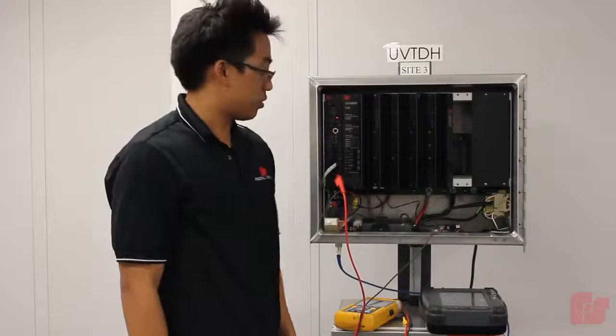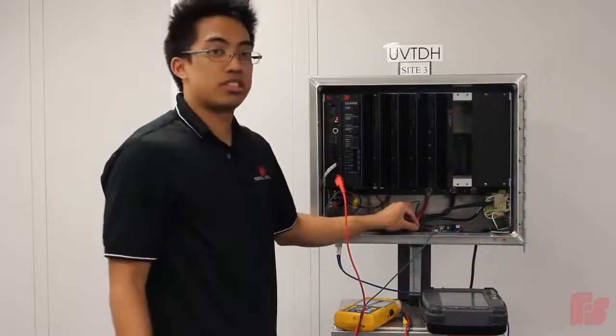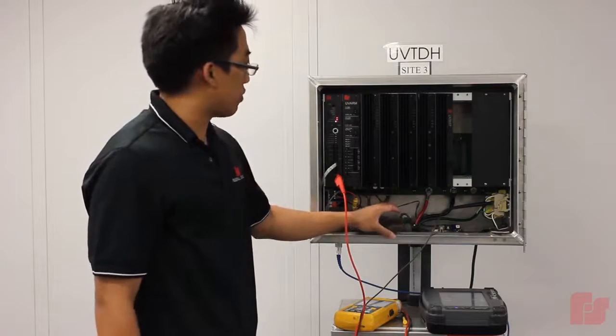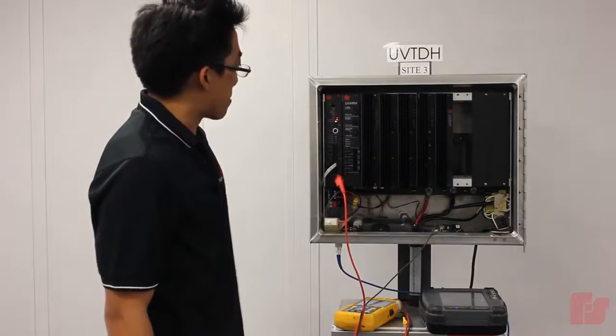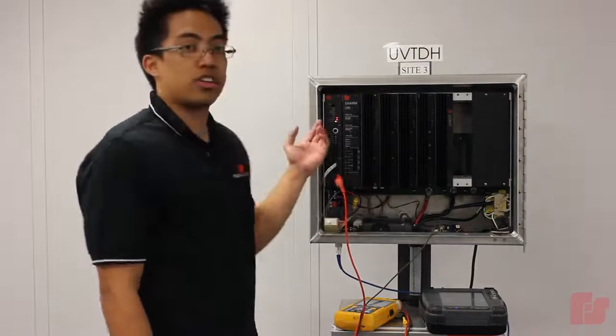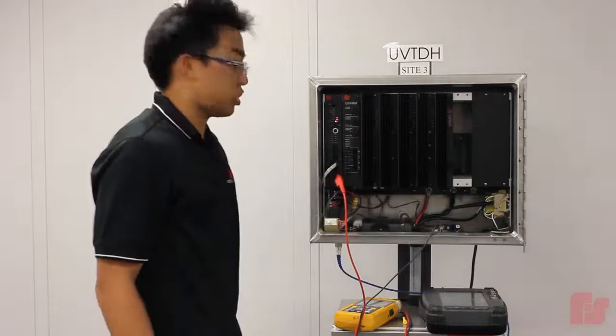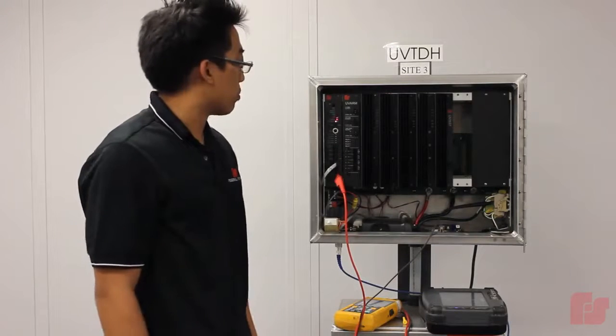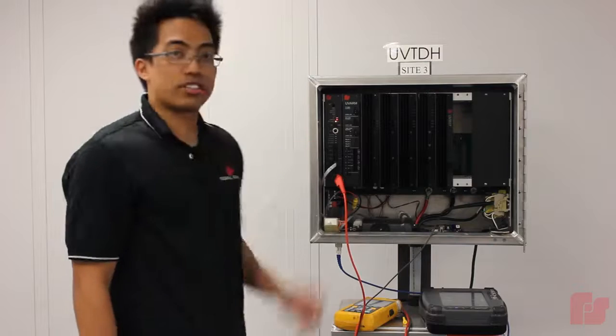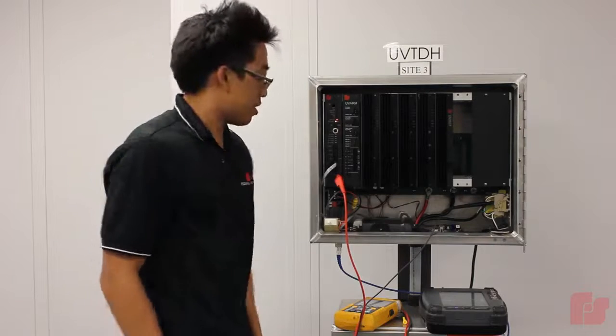So now we're going to go ahead and turn on the calibration tone. And as you can see here, the radio is receiving it and so is the controller board. So the RX level is kind of low and to adjust it to the proper level, we're going to be adjusting the RX gain 1 potentiometer using a precision screwdriver.